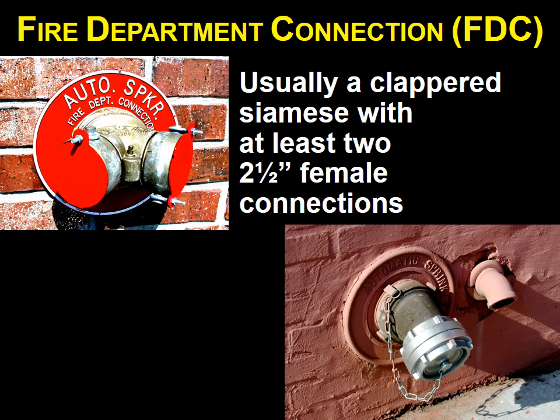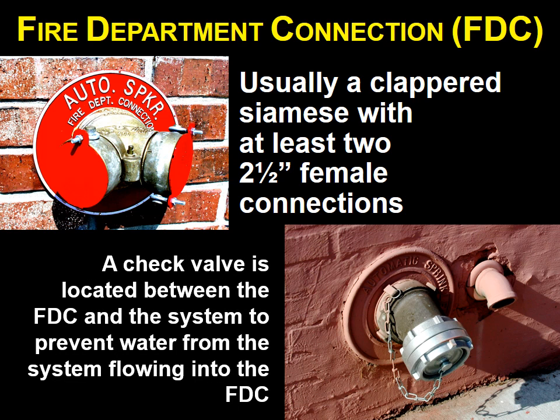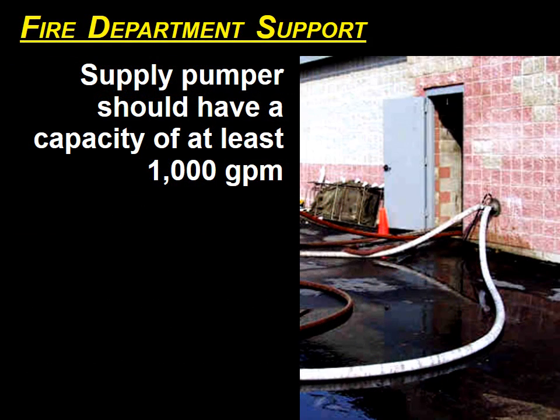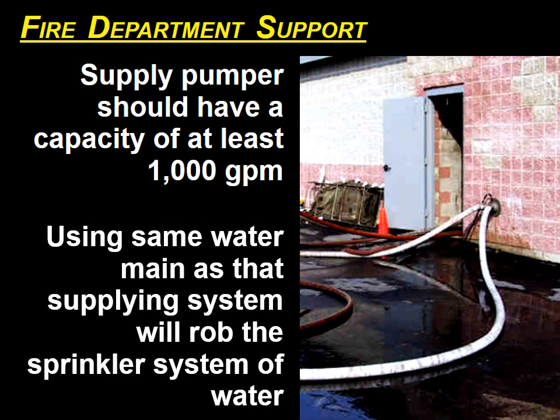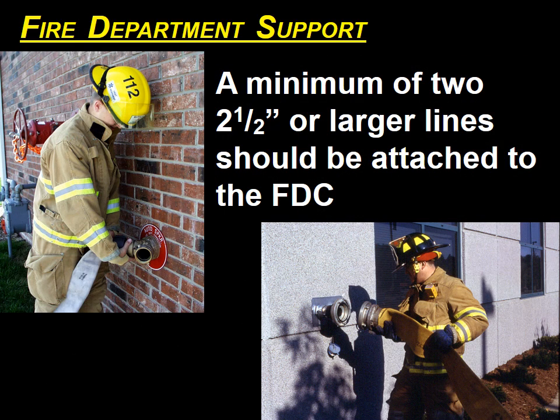Fire department connections: usually a clapper Siamese with at least two 2.5-inch female connections. A check valve is located between the FDC and the system to prevent water from the system flowing into the FDC. A supply pumper should have a capacity of at least 1,000 GPM to supply the FDC. Using the same water main as the supplying system will rob the sprinkler system of water. Again, a minimum of 2.5-inch or larger lines should be attached to the FDC.